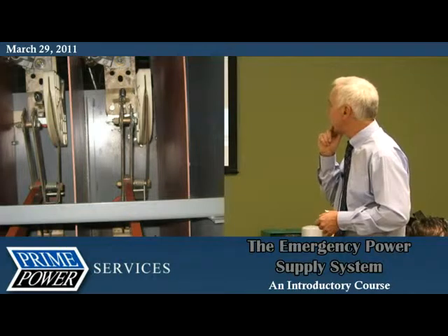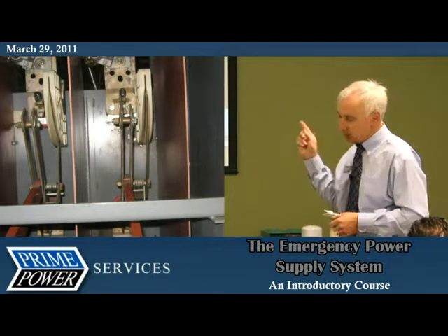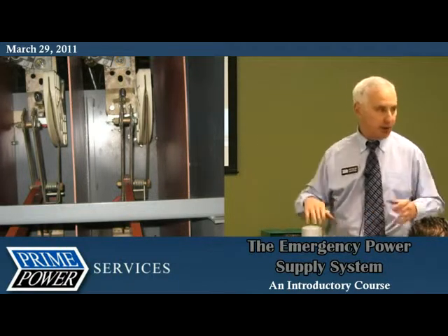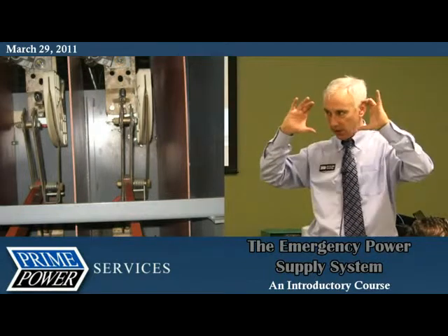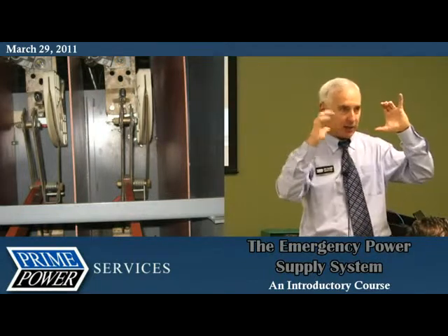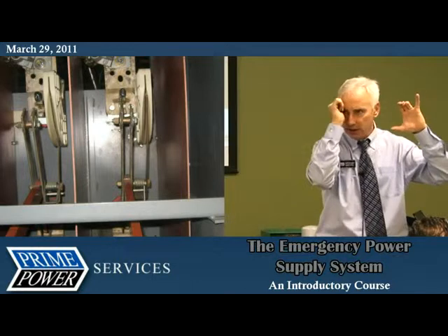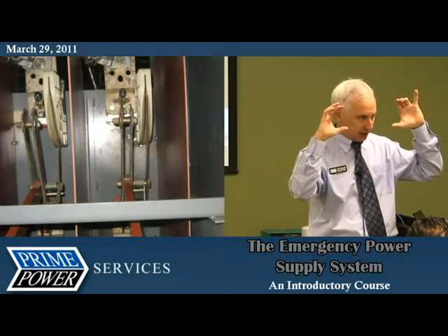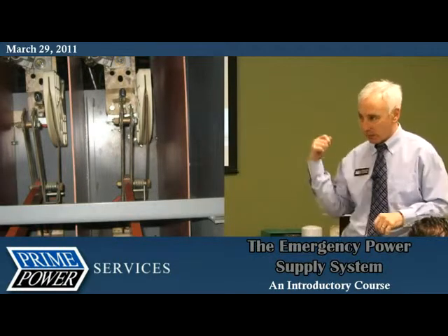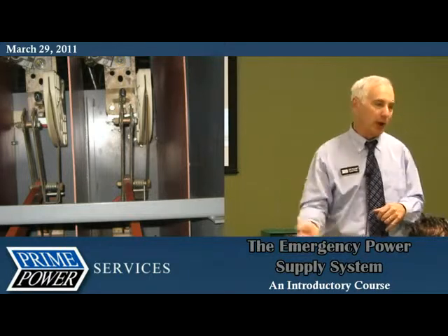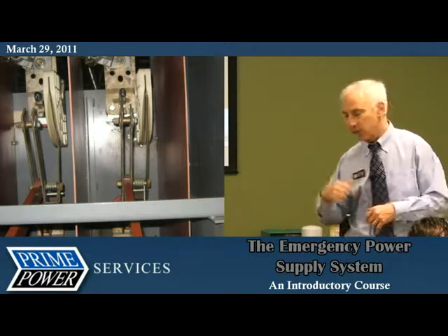The deal with this particular switch is it's open. Whenever you look at a medium voltage switch, it has a window on it, designed so you can shine a flashlight in there and be sure all the phases are disconnected before you open the door. There's also interlocks that won't allow you to open the door if the switch is closed.